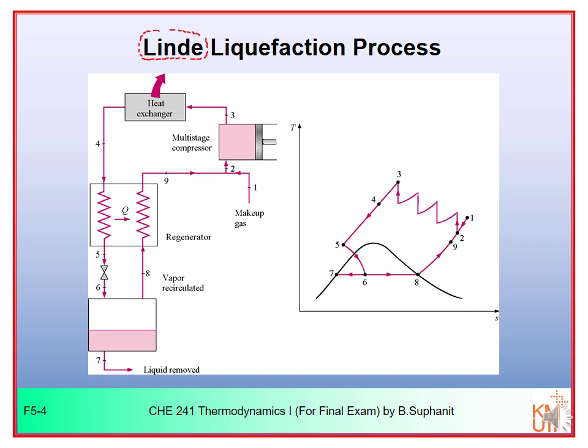In the Linde process, we have a compressor (possibly multi-stage), a cooler, and then the gas flows through a regenerator. This regenerator further reduces the temperature of your gas by exchanging heat with the cold vapor from the flash drum. After exchanging heat inside the regenerator, the cold vapor is returned to the feed point, mixed with makeup gas, and returned to the compressor again.